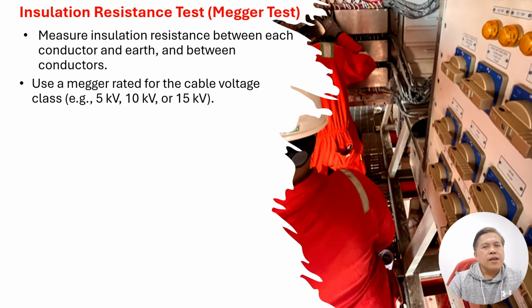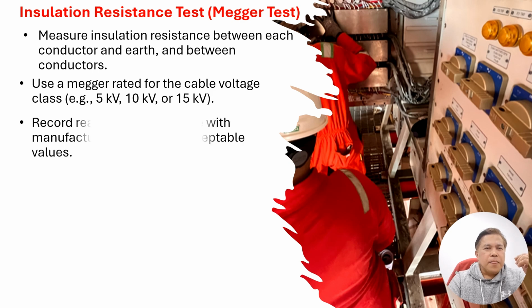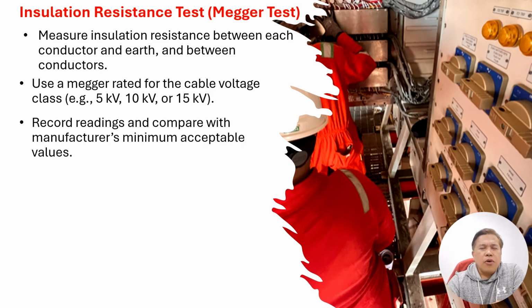So use a megger rated for the cable voltage. What is the test voltage to be used? That's 5 kV, 10 kV, or 15 kV for the high voltage cable that we are using. You need to record all your test results after completion of the test and compare them with the manufacturer's acceptable values. The values that result are to be recorded in the approved form, the checklist and test sheets that we utilize during the testing.